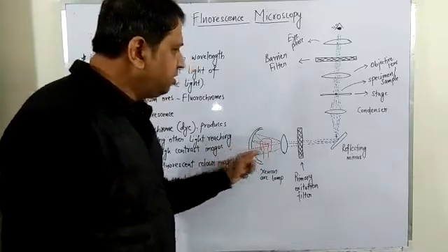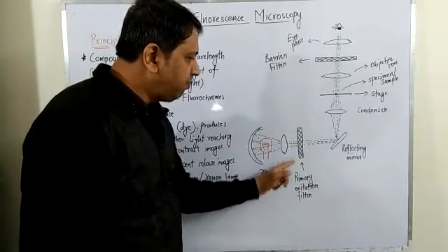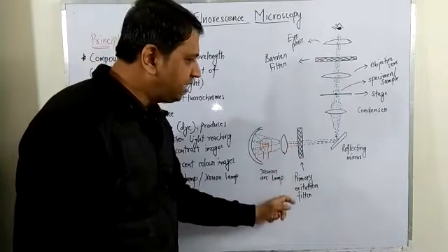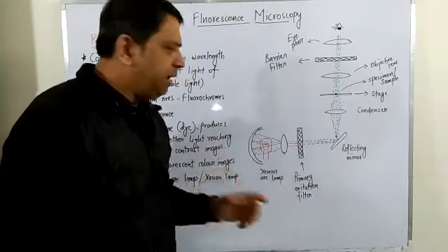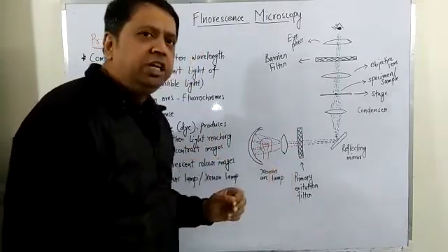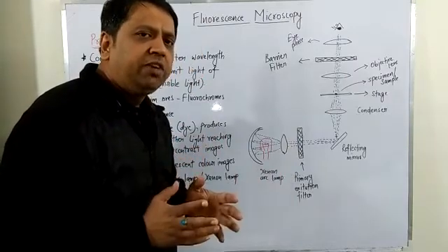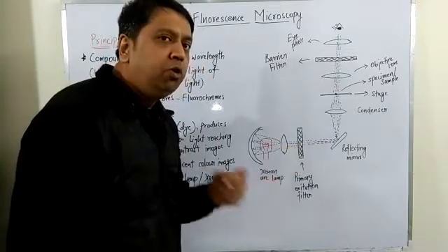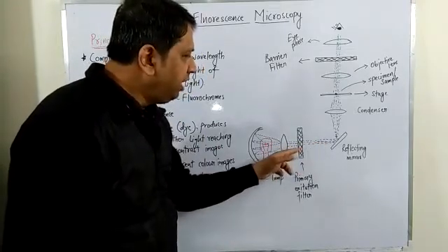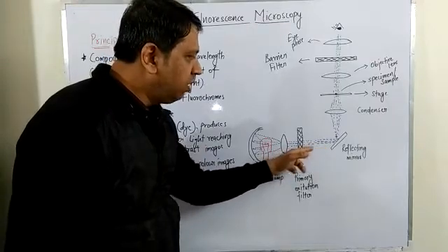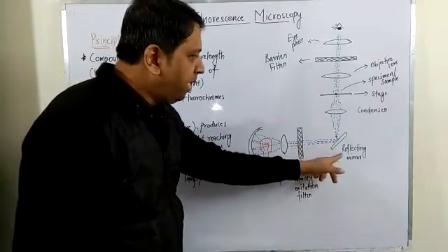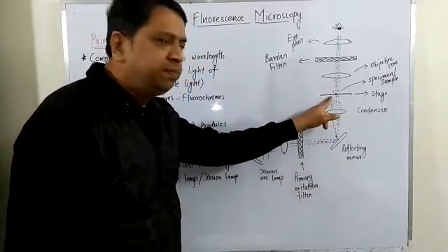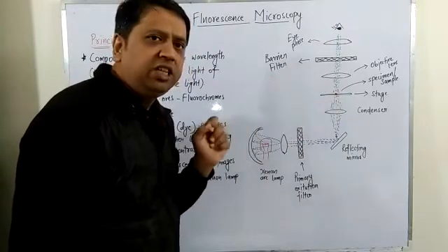This light passes through a primary excitation filter. The function of the primary excitation filter is to cut all kinds of radiation and allow only blue light to pass through. This blue light then passes through a reflecting mirror and condenser, and is focused onto the specimen placed on the stage.